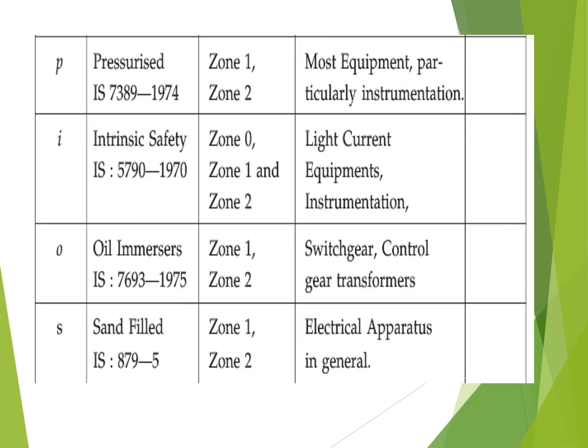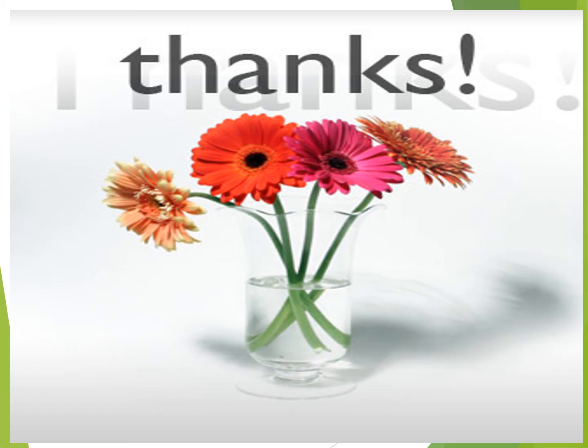Type P, pressurized, zone 1 and zone 2, most equipment, particularly instrumentation. Type I, intrinsically safe, this is very important. Intrinsically safe equipment is applicable to all zones, zone 0, zone 1 and zone 2. It may be used for light current equipment and instrumentation. And type O, oil immersed, is used for zone 1 and zone 2, switchgear, control gear and transformers. And the last, type S, sand filled, zone 1 and zone 2, electrical apparatus in general. So this is about the different types of hazardous zones and the equipment used in them. Thank you.